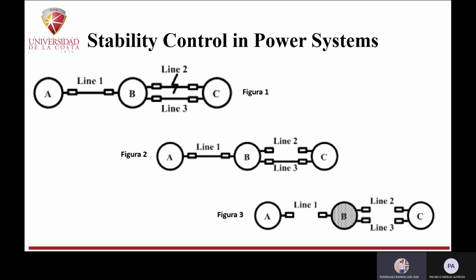At first, a fault occurs on line 2, which might be the result of a branch of a tree reaching line 2. Then the relay of line 2 trips the corresponding breaker, which leads to the power flow of line 2 transferring to line 1 and line 3. After a time delay, the overload relays of line 1 and line 3 act and trip the corresponding breakers in line 1 and line 3. Finally, system B is isolated. A blackout will occur in system B if there are no backup power supplies in it.